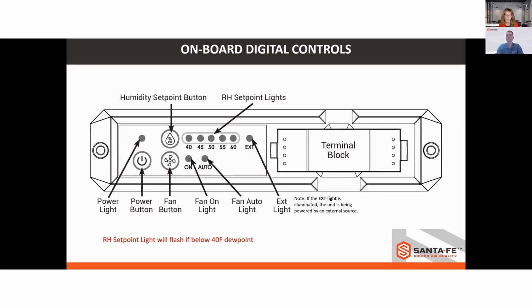So you can run the fan on auto, which means it'll only run when the dehumidifier and compressor is running to remove moisture, or you can also run it on continuous as well. And then with that 40-degree dew point cutout that we talked about as a new feature, the RH set point that you have it set on will flash when the dew point is below 40 degrees dew point. And that dew point really is important because it's a great feature that will extend the longevity of the dehumidifiers, but prevent it from going into defrost mode as much as well.